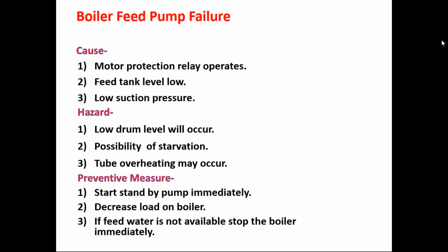Then how to prevent this boiler feed pump failure? Start the standby pump immediately. Decrease load on the boiler. If feed water is not available, stop the boiler immediately. So all these three things can be done to prevent boiler feed pump failure.